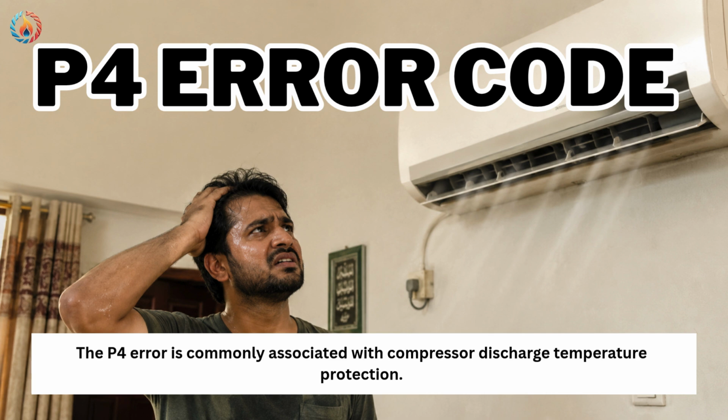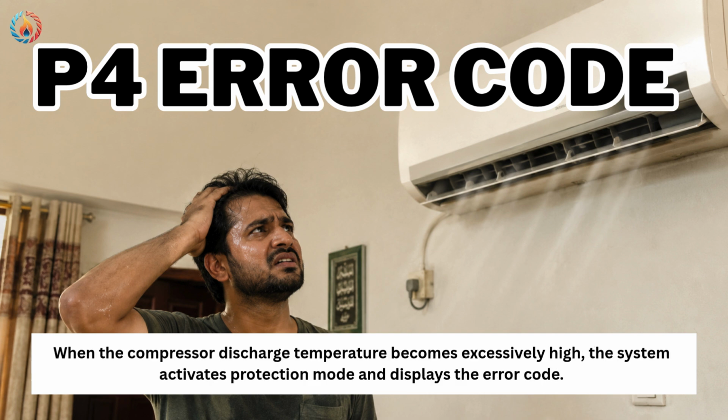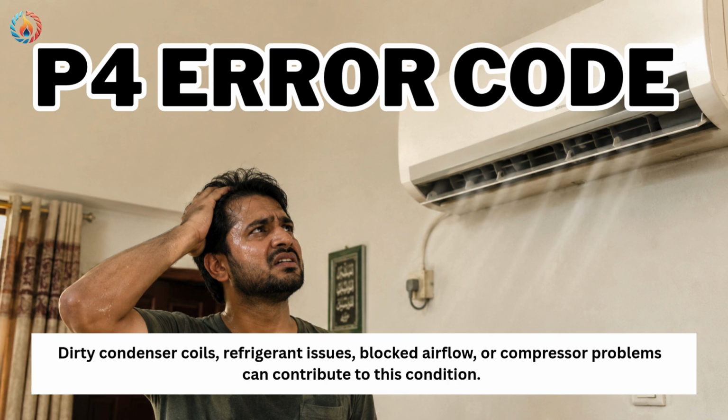P4 error code. The P4 error is commonly associated with compressor discharge temperature protection. When the compressor discharge temperature becomes excessively high, the system activates protection mode and displays the error code. Dirty condenser coils, refrigerant issues, blocked airflow, or compressor problems can contribute to this condition.